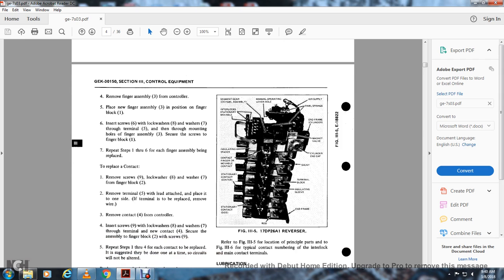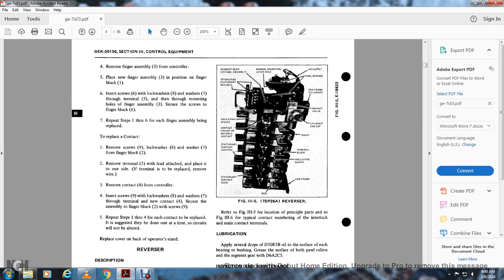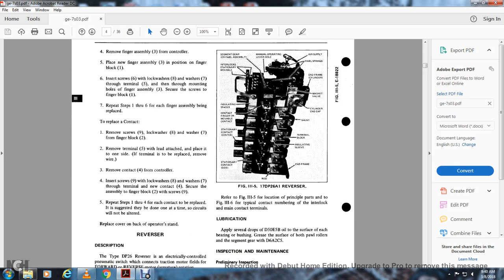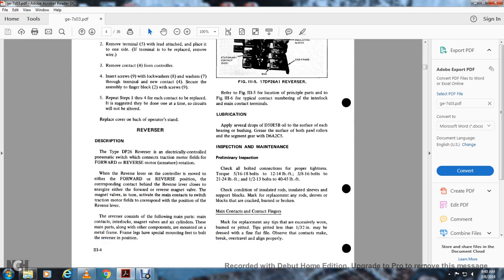To replace the contact, remove the screws 9, lock washers 8, washer 7, from the finger block 2. Remove the terminal 5 with the lead attached, placing it to one side. If the terminal is replaced, it can be removed with the wire. Remove the contact 4 from the controller. Insert the screws 9, lock washers 8, washer 7 from the terminal. Install the new contact 4. Secure the assembly to the finger block 2 with the screws 9. Repeat steps 1 through 4 for each contact to replace. It's suggested that they be done one at a time so the circuits are not altered. Place the cover over the operator's stand.